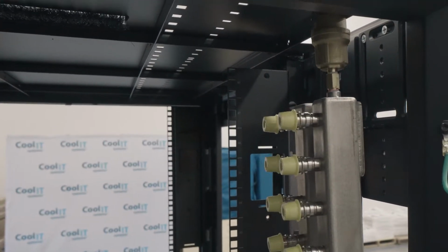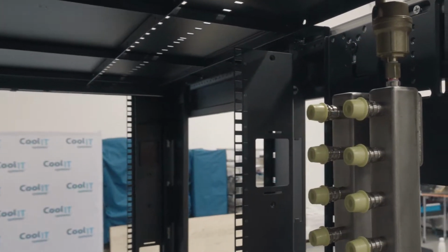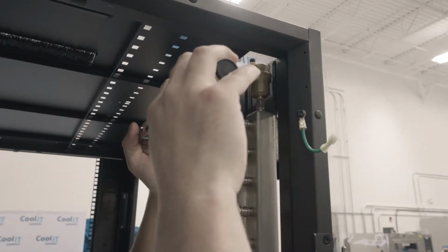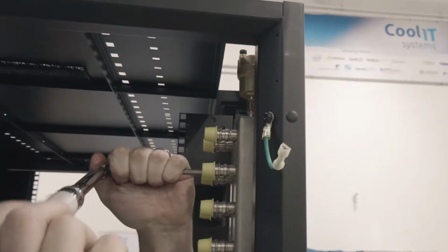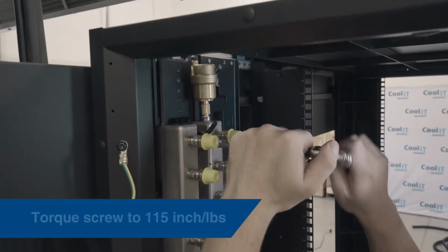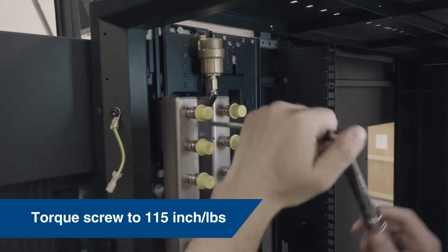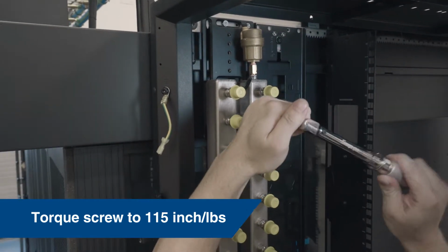Install the manifold into the rack by hanging the manifold mounting bracket onto the J-hook in the rack. Secure the manifold to the rack with the included hardware and leave the J-hook in place. Ensure all screws have been torqued to 115 inch-pounds before continuing.